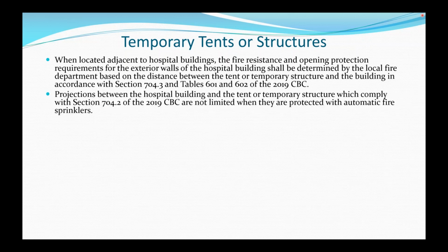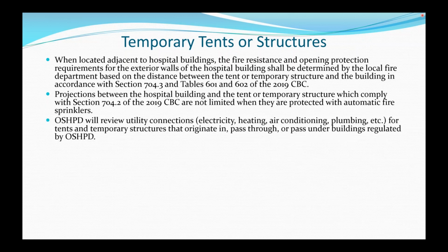Projections between the hospital building and the tent or temporary structure shall comply with the building code and are not limited when they are protected with automatic fire sprinklers. OSHPD will also review utility connections for tents and temporary structures that originate in, pass through, or pass under the buildings regulated by OSHPD. Again, if you can do standalone power or bring it in from somewhere else, it's going to be a lot easier, but you do always have the option to use hospital power.